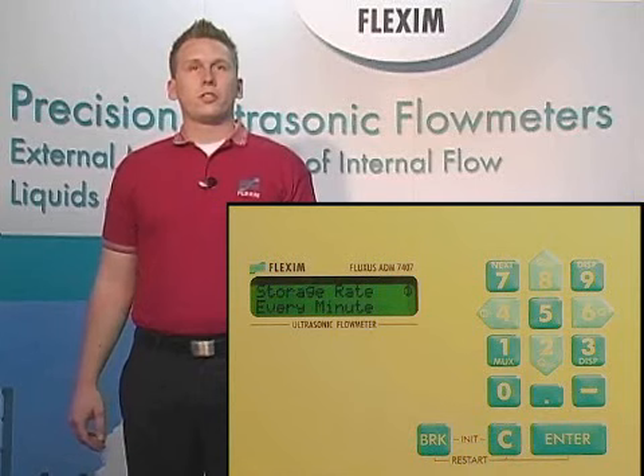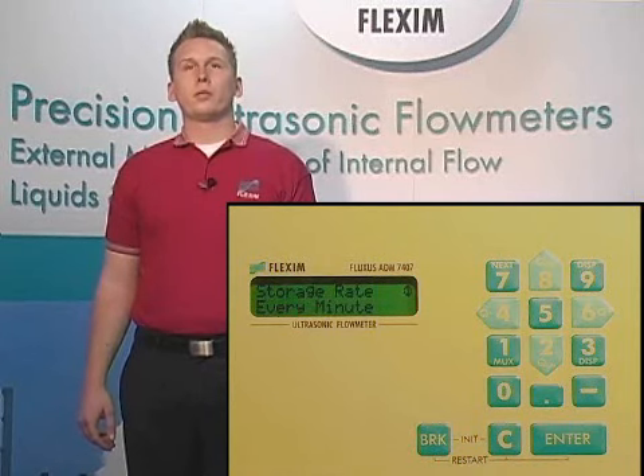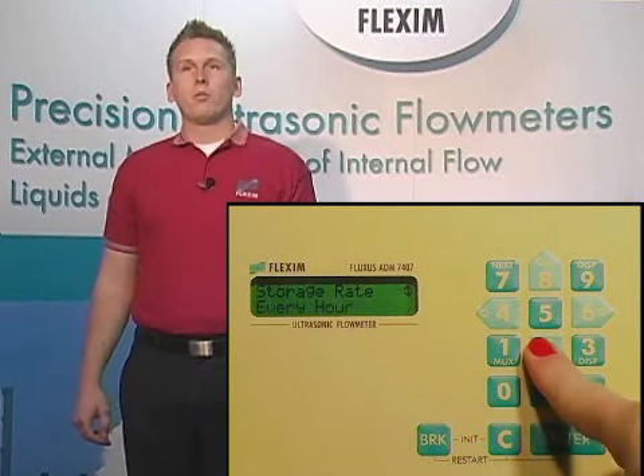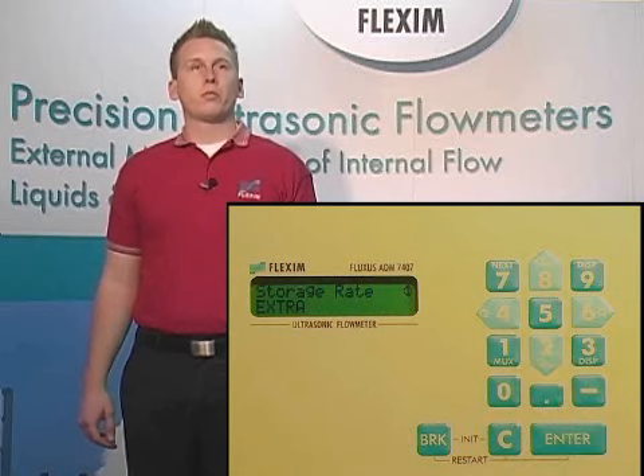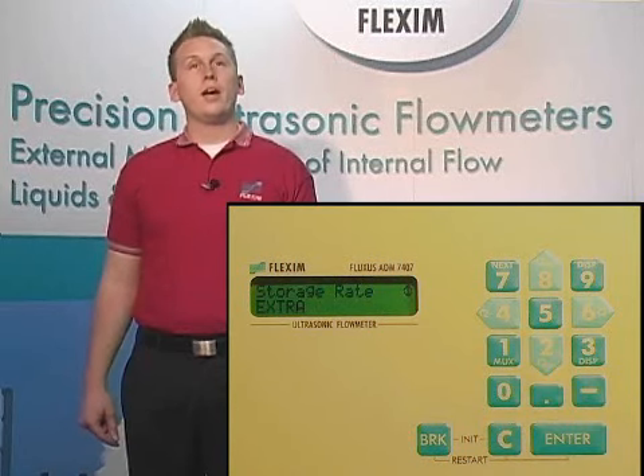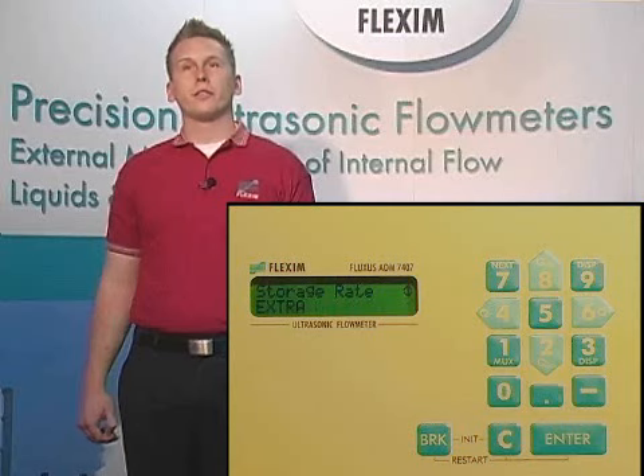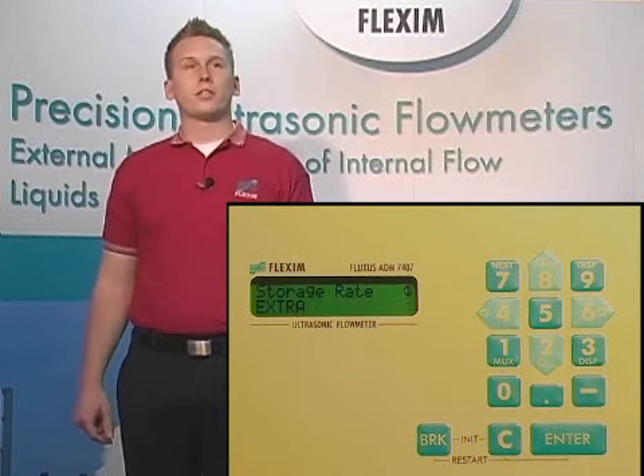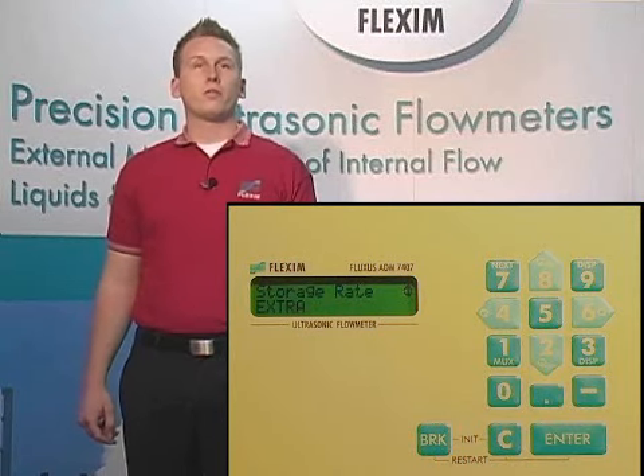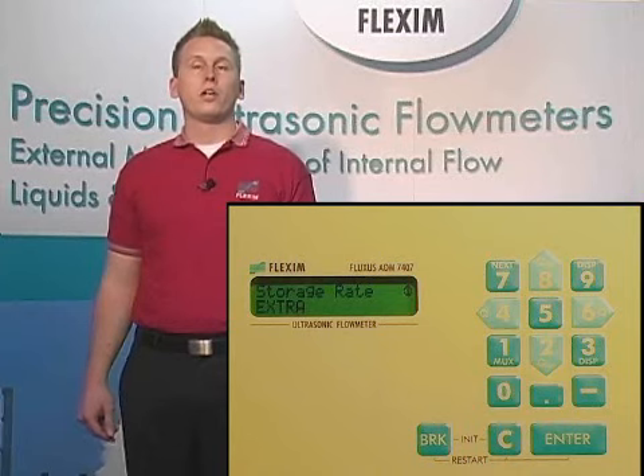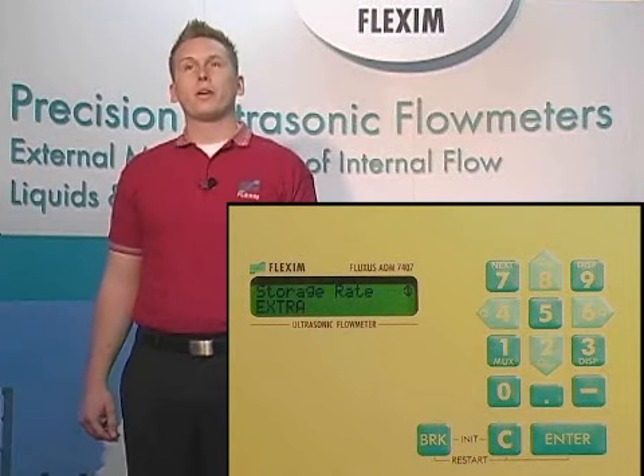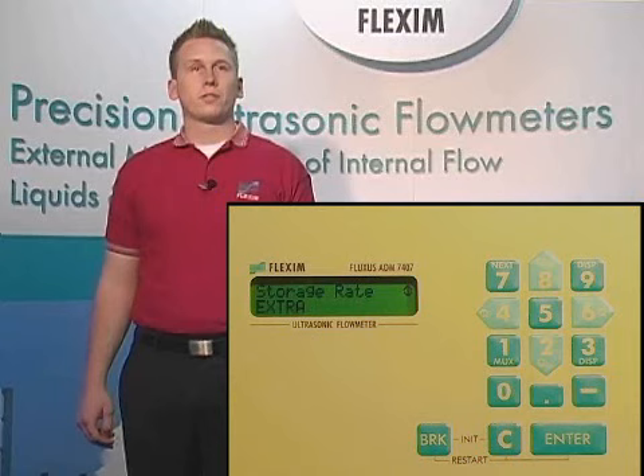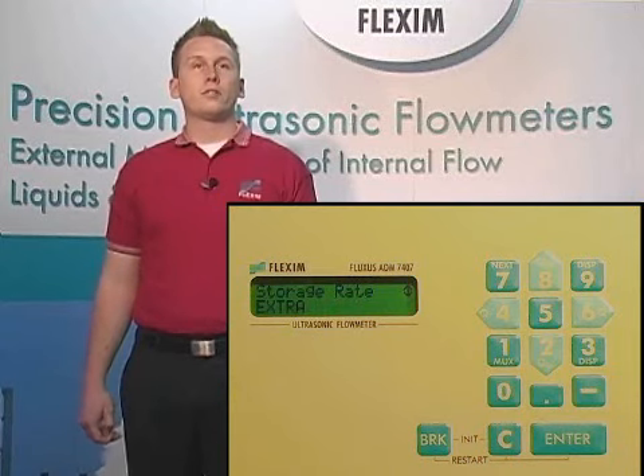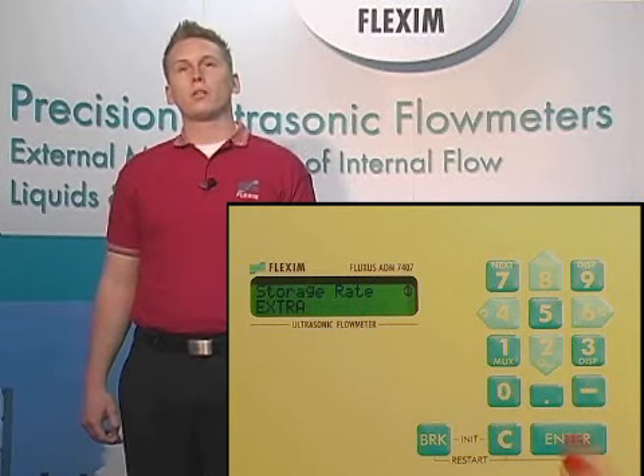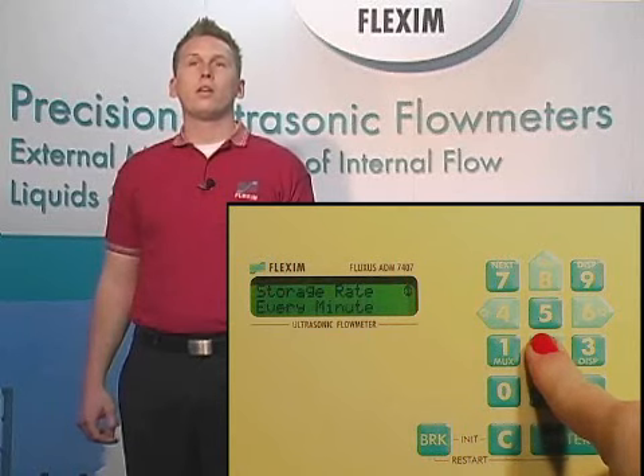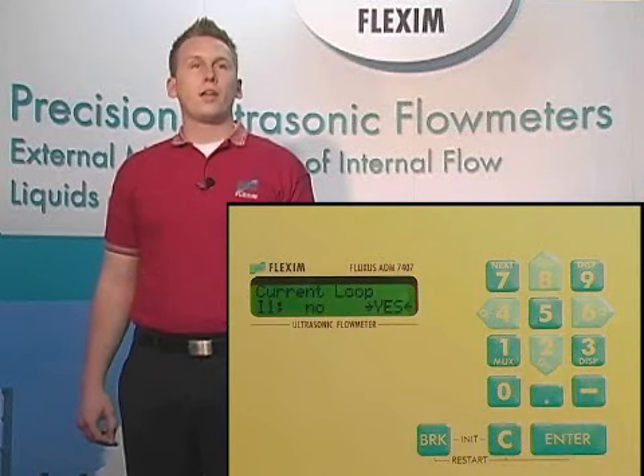Storage rate allows us to choose how often to store a data point into our internal data logger. Once a minute is fine for a measurement over 20 or 30 minutes. Once an hour is fine for a measurement over a day or two. Using the data logger set to once per second, we have just over 24 hours of storage capacity, or at once per minute, we have about 70 days of storage capacity. However, you could set this value to record as infrequently or as often as you'd like. For now, let's set this to once per minute and hit enter to confirm.